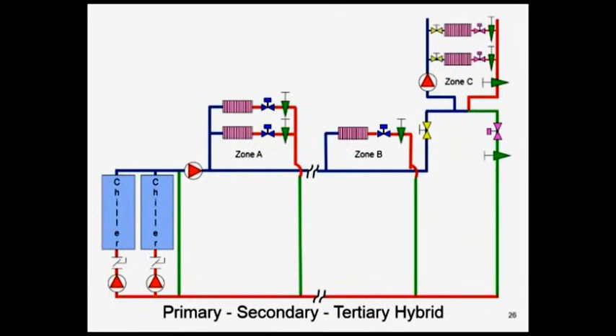Here's a combination, primary, secondary, tertiary. And I say combination, look at zones A. Zones A are closer buildings to the chiller plant, and there's no tertiary pump. Look at zone C. It's the furthest one out, and it don't have enough differential pressure from the secondary pump to pump zone C, so we had to put a tertiary pump. We had to put another bridge out there. The point of this discussion is recognize a simple sketch is required for you to understand how to balance zone A, zone B, and zone C. Otherwise, you don't have a chance of balancing. And this would be called a primary, secondary, tertiary, kind of a hybrid.